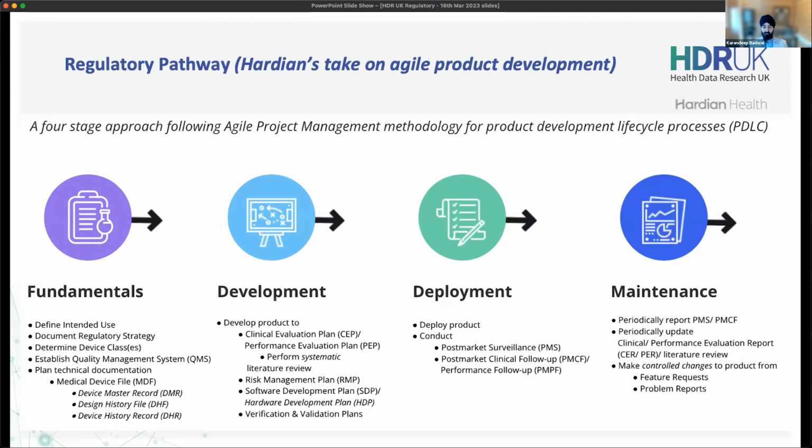So, for example, if you have a device that's made for physicians, let's say a cardiologist with over 10 years of experience, you can put technical jargon into the IFU and instructions because they're going to understand that terminology. Now, if this is going to be used by somebody at home, they may not understand that terminology. So the intended use statement, as we're going to touch on later today, is effectively the backbone of your medical device. It shows you what that medical device actually is and what the indications are.